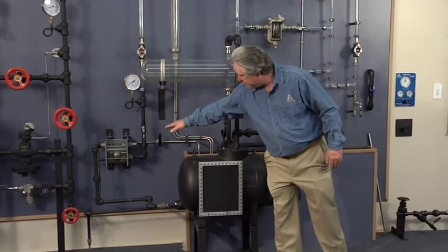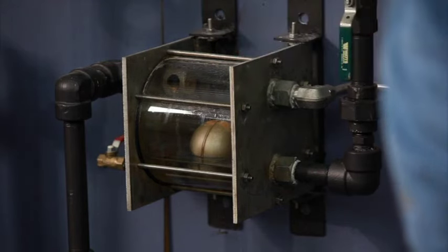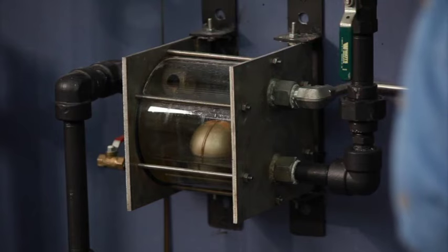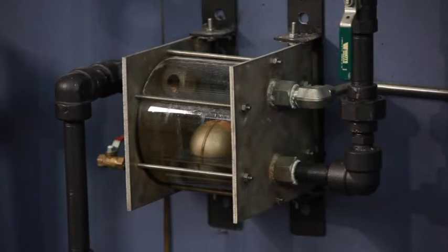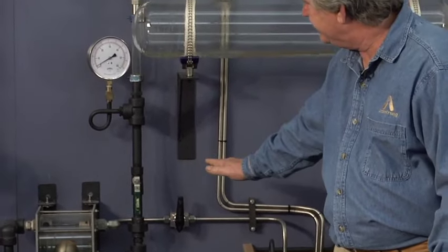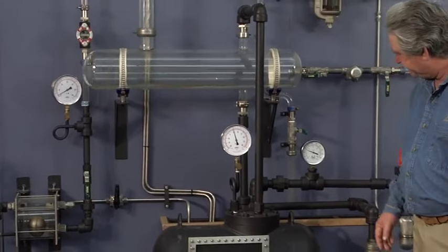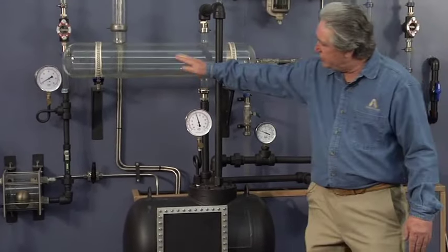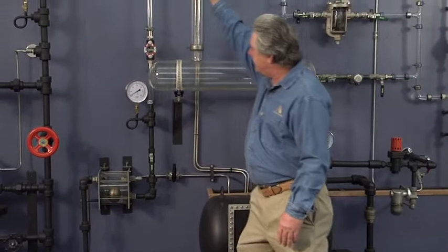You can see now that there is flow coming into the trap. And as we slowly start to build pressure in the pump body, you'll see the pressure slowly build here. As that happens, we will continually pump liquid into and out of the trap and into the header. And we should, as the pressure builds in the pump, we should see a flow through the vertical rise here.